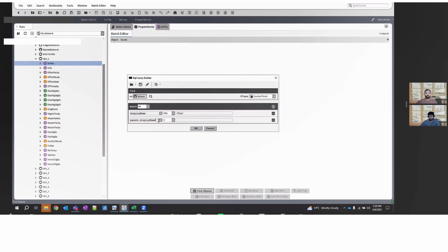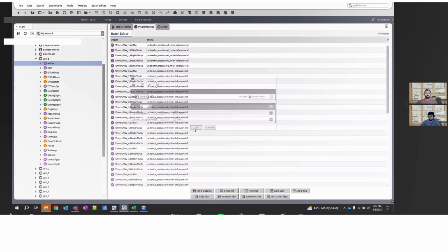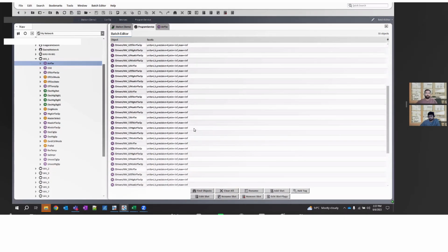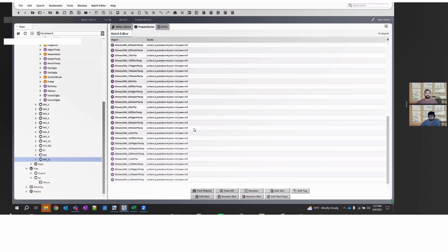I'm using a query on parent display name, defining that the point should have a display name of flow, but it should also have the parent name as VAV. Once I do that, it will list all the points having parent VAV, and in this case it's all the folders, 11 VAVs here.